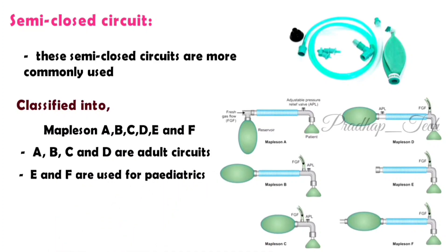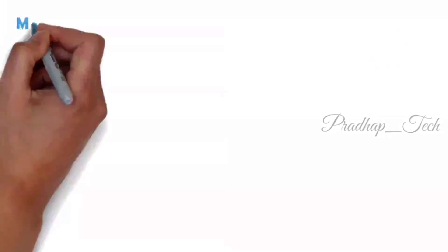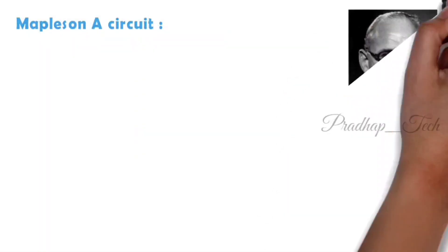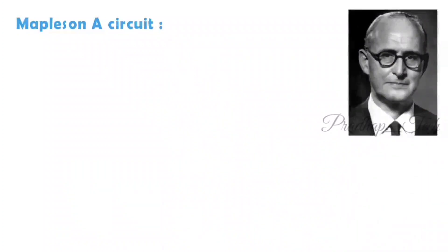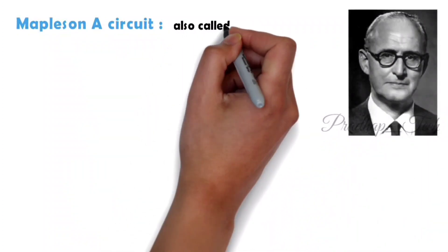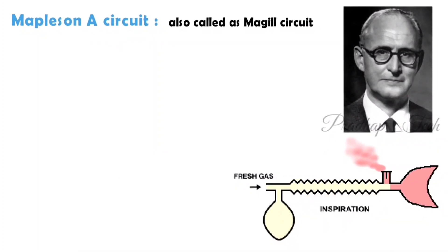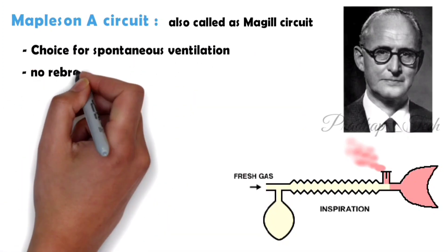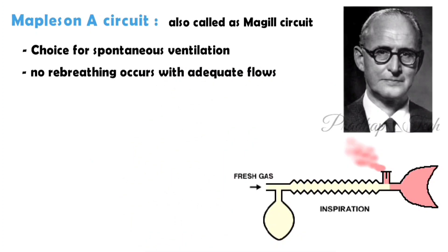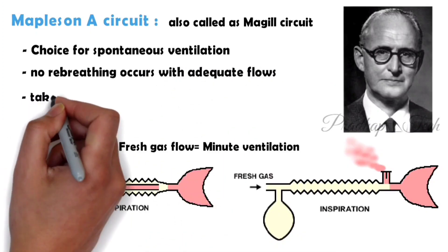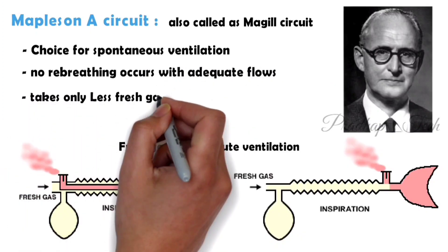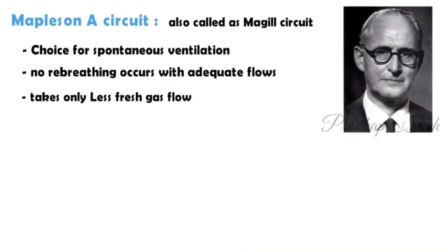Now, we'll discuss Mapleson A circuit. Mapleson A circuit was founded by Ivan Magill, so it is also called the Magill circuit. The fresh gas flow is near the reservoir bag and the expiratory valve is near to the patient. This circuit is the circuit of choice for spontaneous ventilation because there's no re-breathing with adequate flows. It takes only less fresh gas flow, so it is the best circuit for spontaneous ventilation.